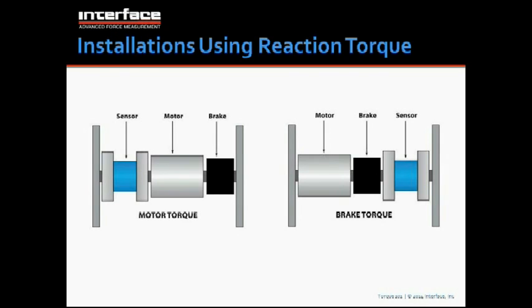Some more examples of reaction sensors measuring rotary torque. You have a motor that's mounted to a torque sensor rigidly, and then the shaft is actually attached to a brake. You see the left side, we're trying to measure motor torque, so basically maybe we're testing a motor, and so the sensor is actually connected to the motor, and we're using the brake to provide the load. On the right, you have a similar but different setup where we have the motor connected directly to the brake, and then the sensor actually holds the housing of the brake. And so as you apply your load with the brake, the housing of the brake wants to rotate, and the sensor is used to prevent that.